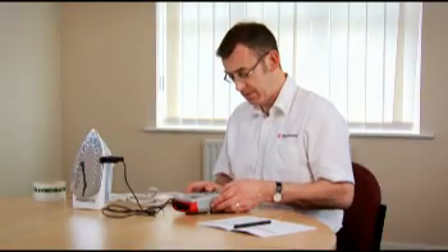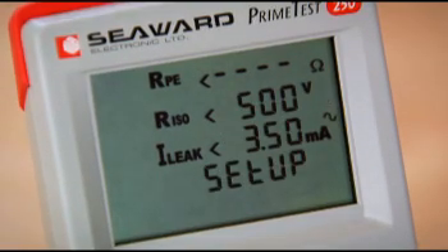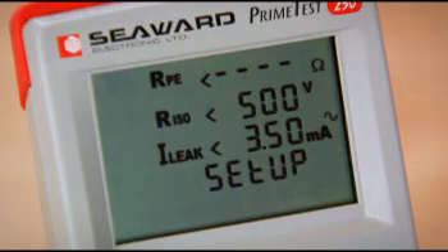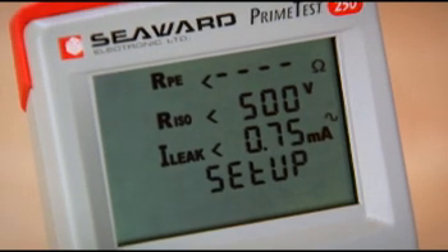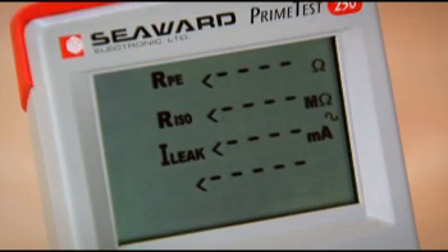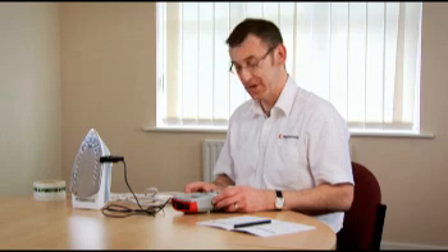and before we start we're going to select the insulation test voltage and the leakage limit for this appliance. So we press the setup key. We've selected 500 volt insulation test and a 0.75 milliamp leakage limit. So the tester is now ready to go. Make sure the appliance is switched on and push the Class 1 button.